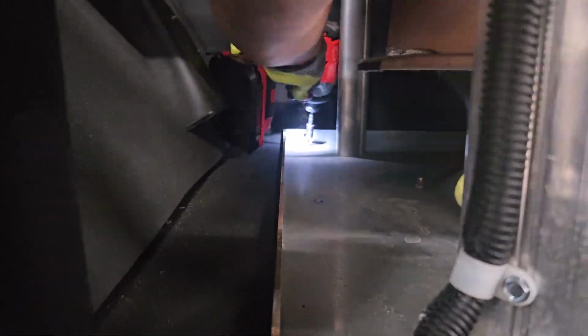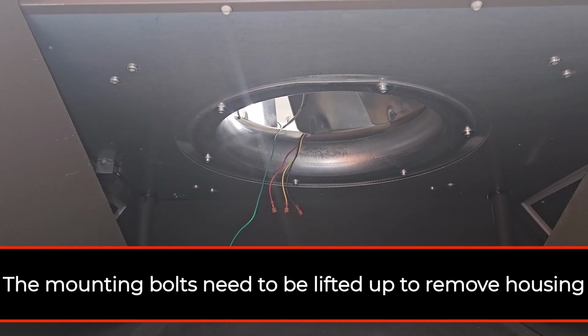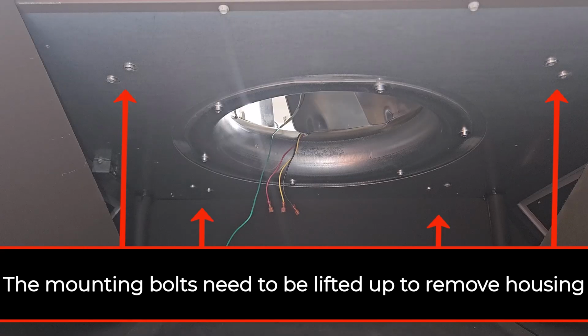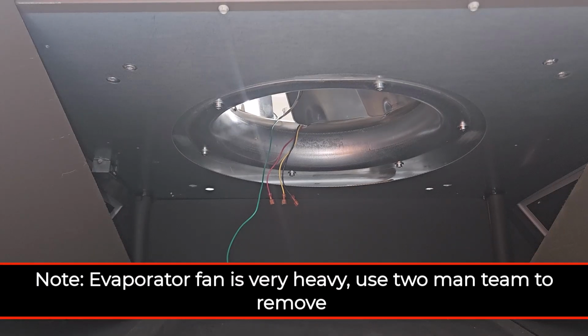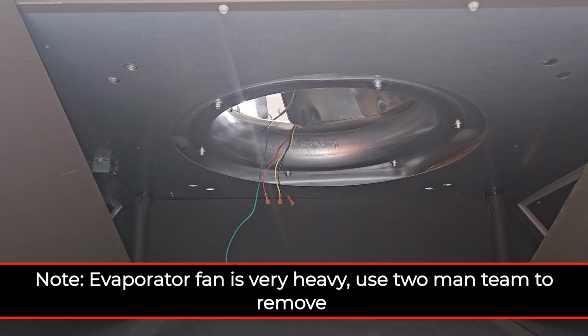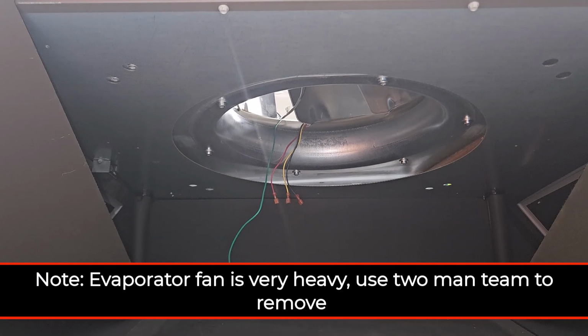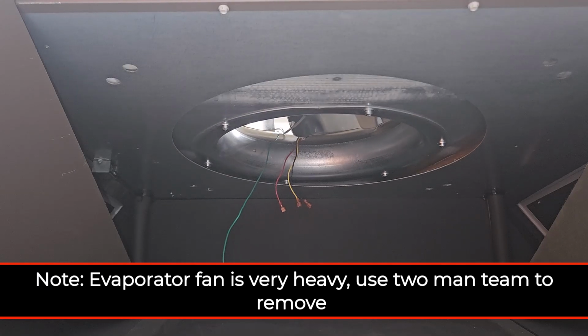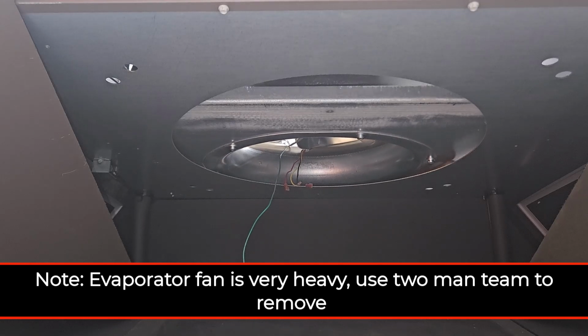A 5/16 magnetic chuck can be used to remove the mounting screws. The mounting bolts holding the housing are recessed into the MEGA-TEC frame. This makes it difficult to pull the evaporator motor housing from the machine. I used a broomstick and inserted it beneath the motor assembly, and this will lift the back mounting bolts out of the recess so the blower assembly can be pulled forward.